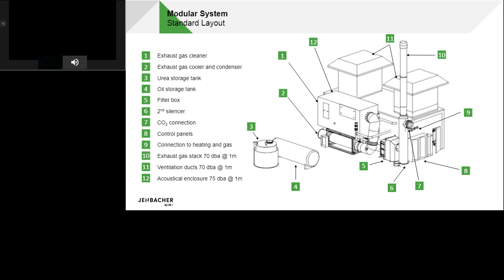Numbers 10, 11, and 12 on the screen show the exhaust stack. We're trying to keep that at 70 dBA at 1 meter, which is pretty strict. The ventilation ducts, number 11, are actually the ventilation, I shouldn't say exhaust, drawing air through and across the generator to keep it cool and then exhausting it into the atmosphere. But again, those fans create sound, so we're attenuating that sound as much as possible. And then overall, number 12 is the acoustical enclosure, and we can make that to whatever site requirements are necessary. In this case, we're showing 75 dBA at 1 meter, which is a pretty strict level.